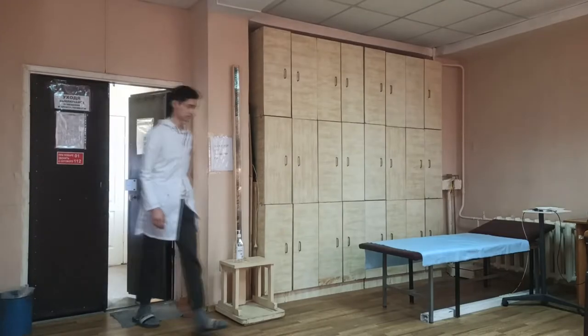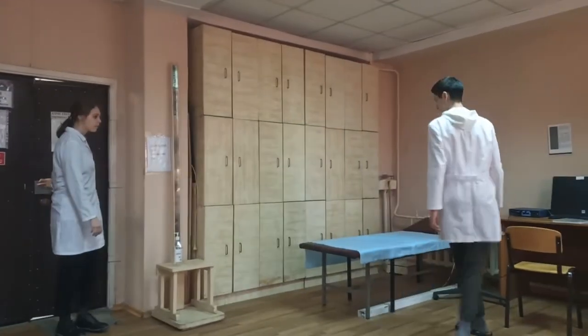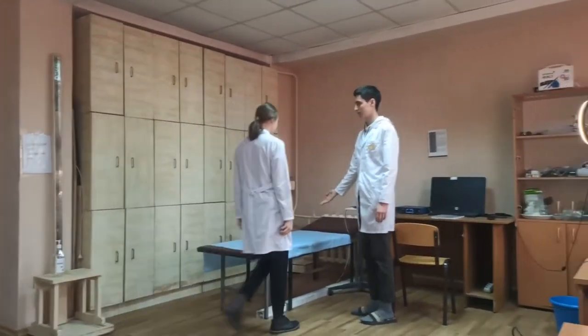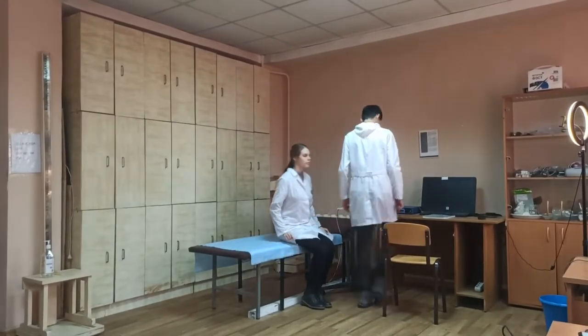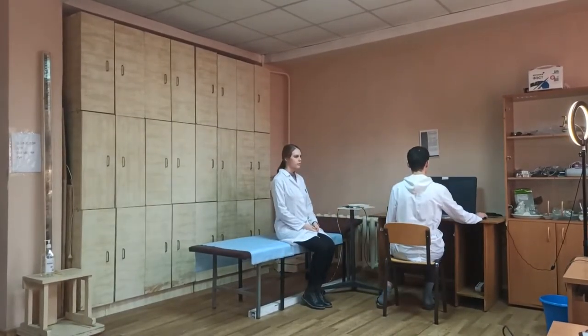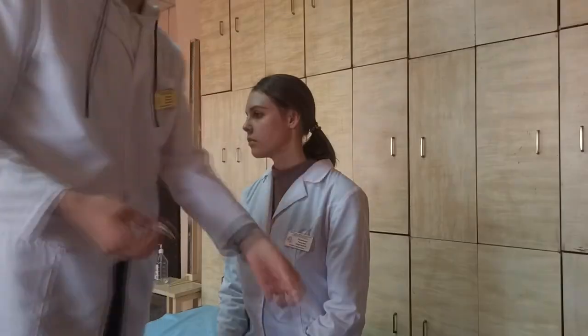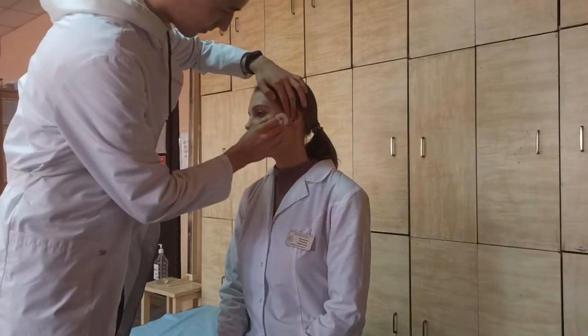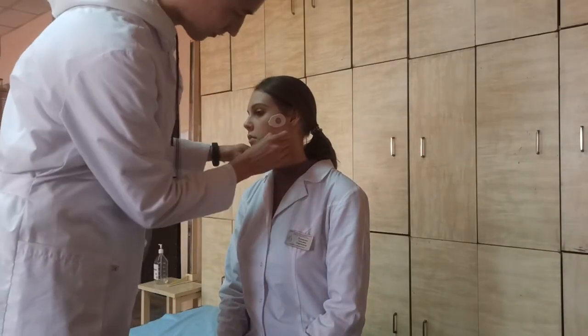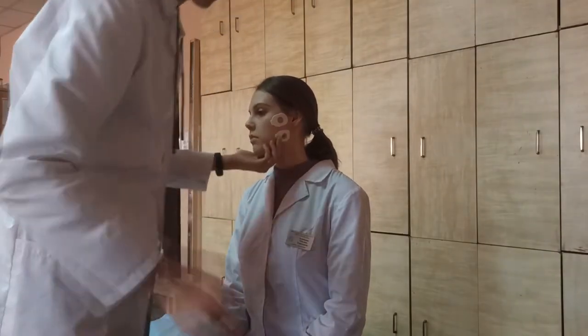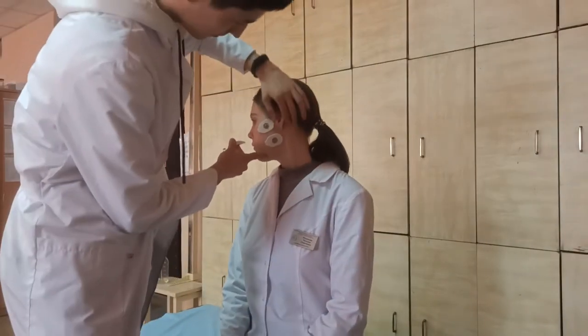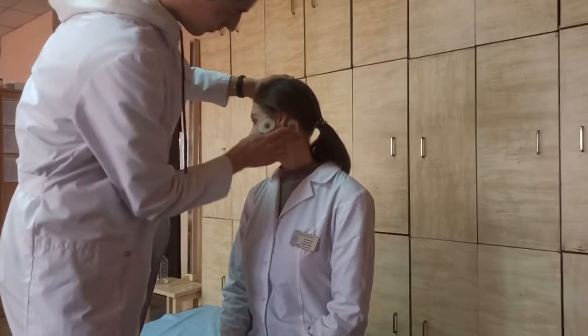For execution of EMG, we go into the room with equipment. Invite the test person to sit down on the bed. Attach the electrodes at the location of the motor points, and one more, the black grounding electrode, in the area of the mastoid process. Motor points are areas with the greatest muscle tension, which are determined by palpation during muscle tension.